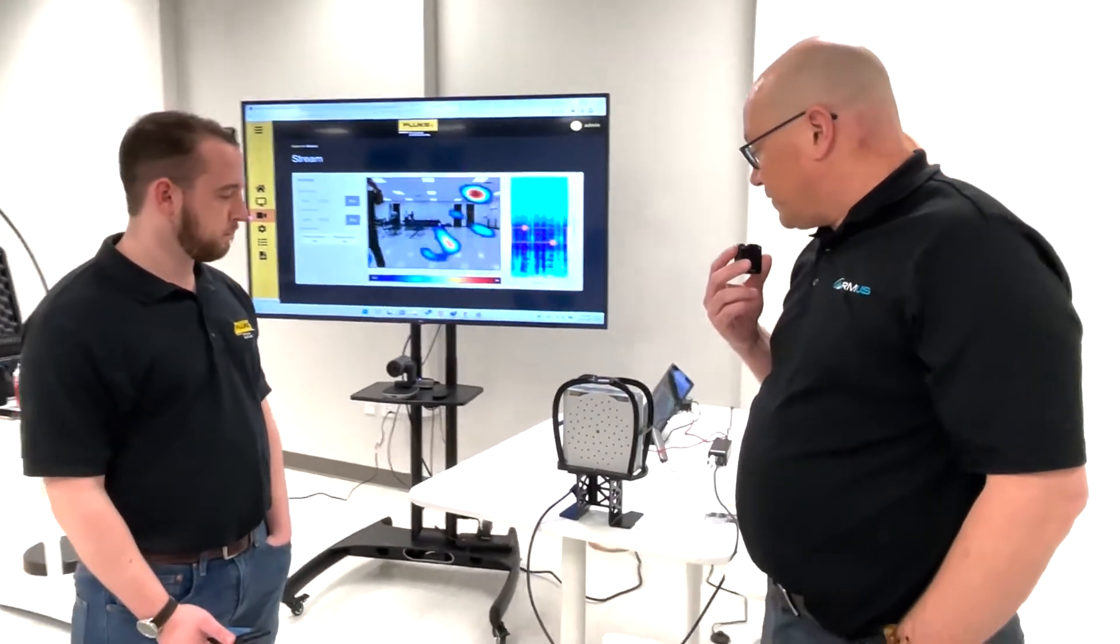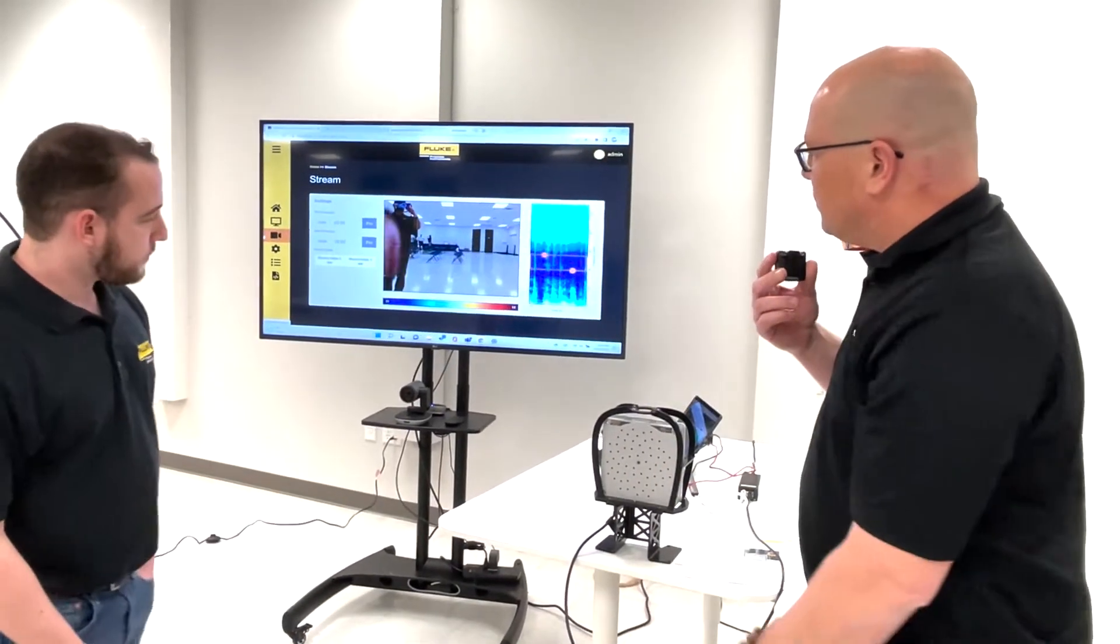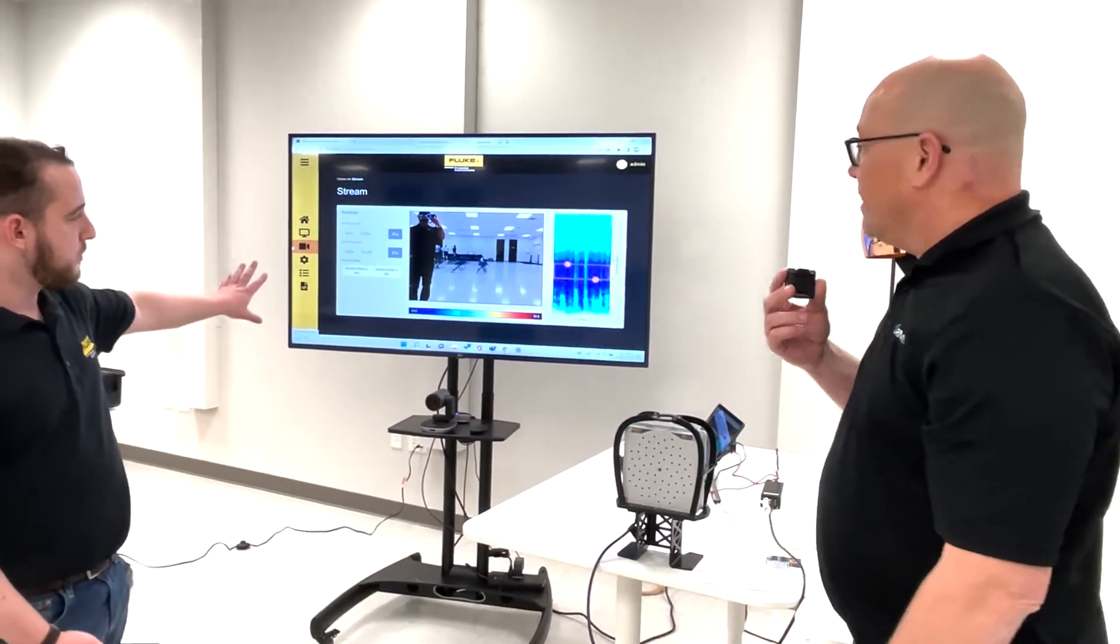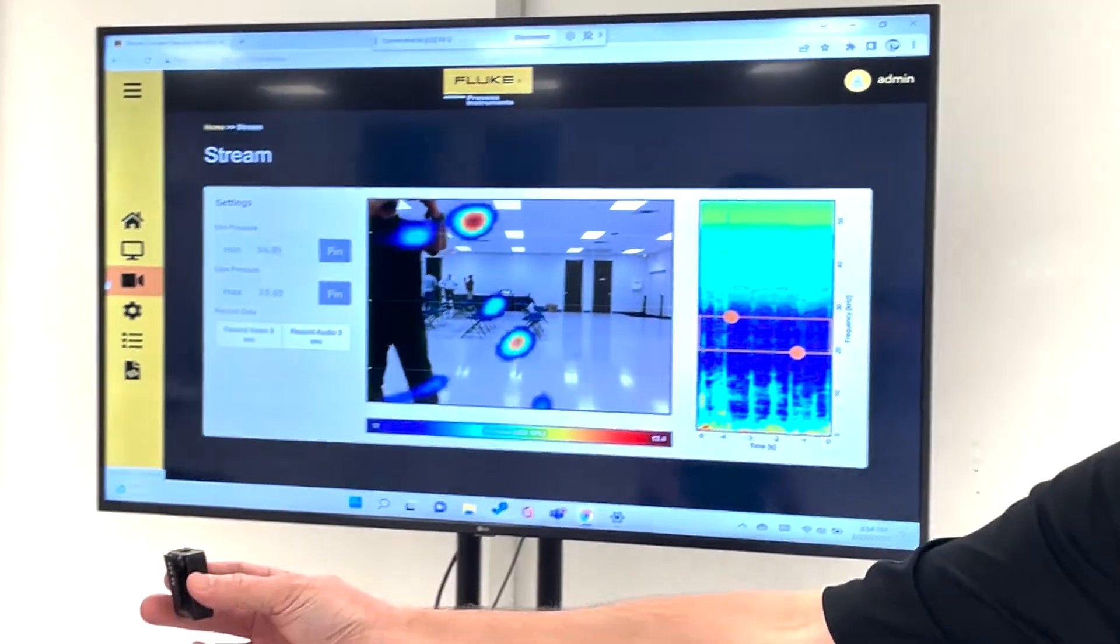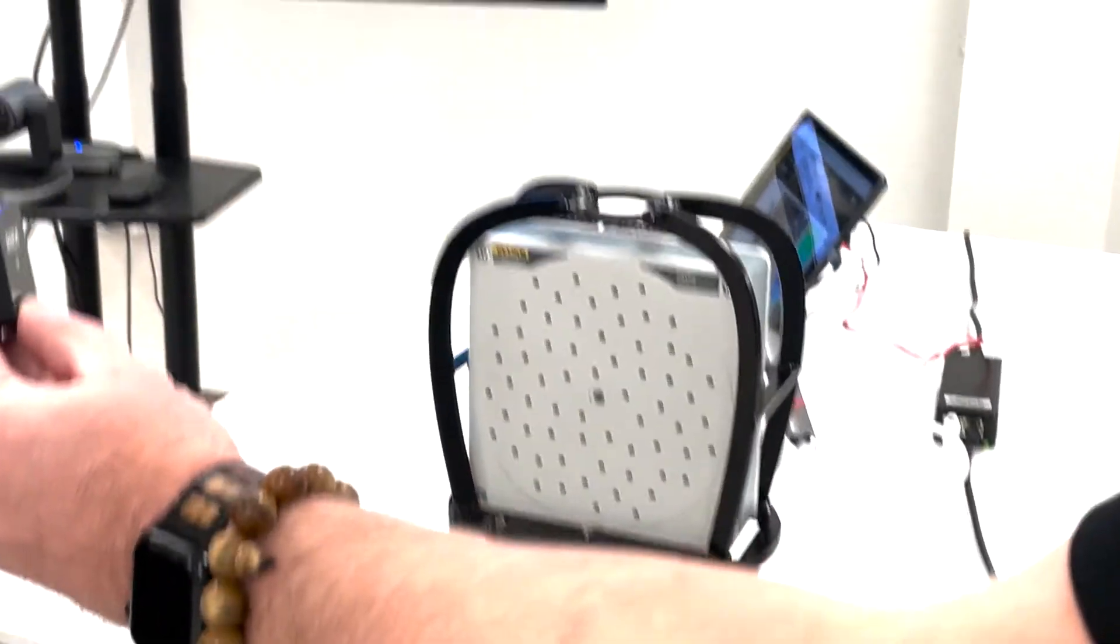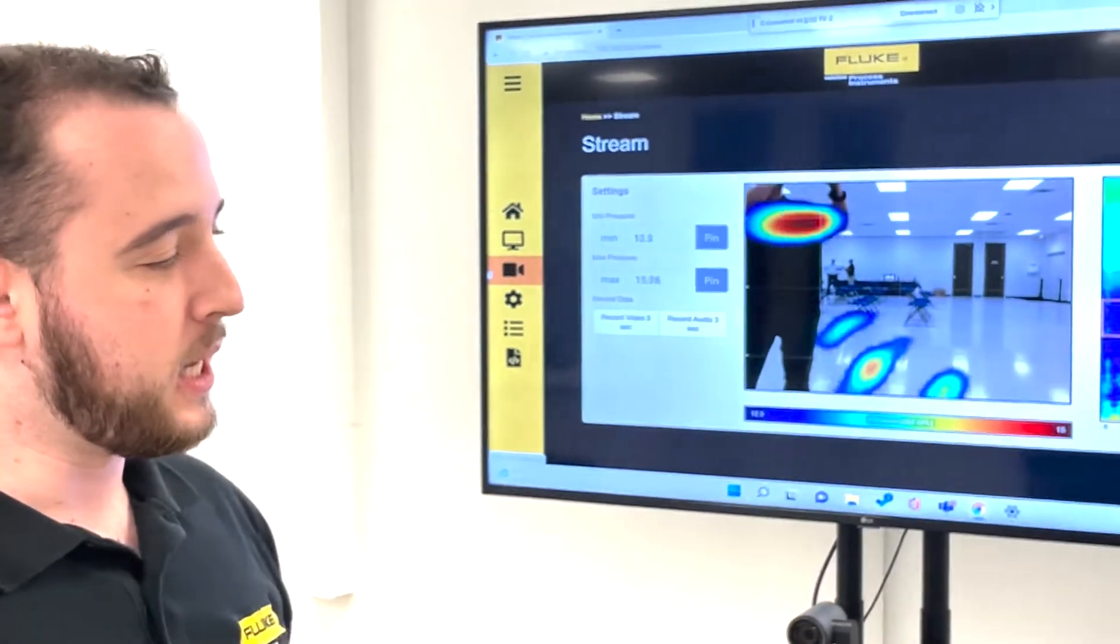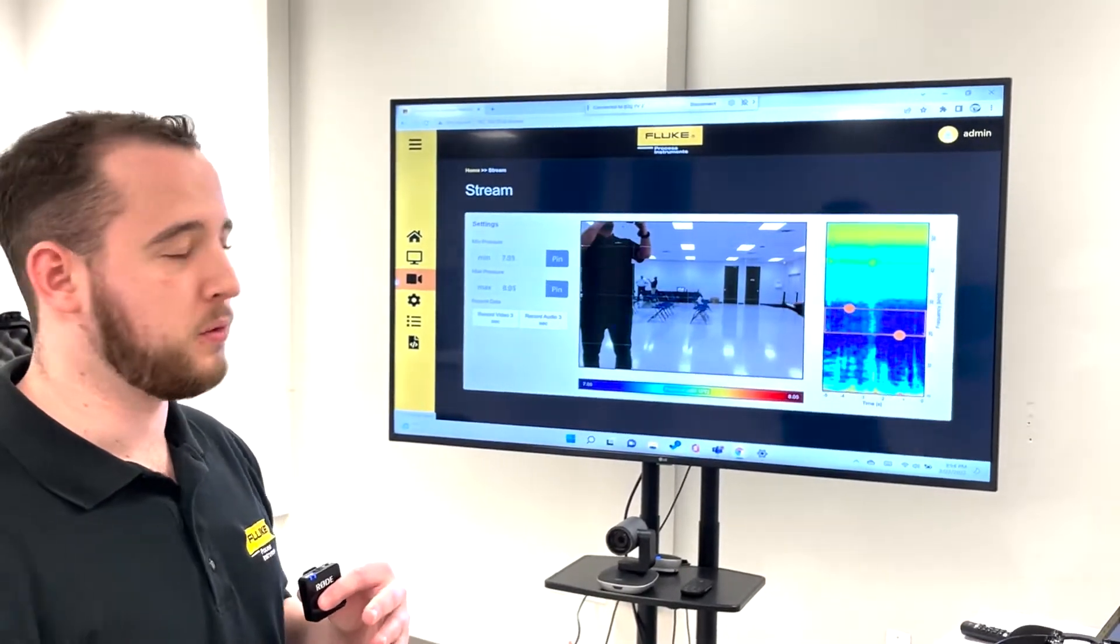And so what do we have here? What we're seeing in the background here is actually a visual representation of sound. We're viewing the web server of the device right now. We're just plugged into the laptop here for demonstration purposes, but on the acoustic camera itself, we've got 64 MEMS microphones with a visible camera right in the center there. What that is doing is overlaying the sound intensity for all of those microphones on top of that visible feed.